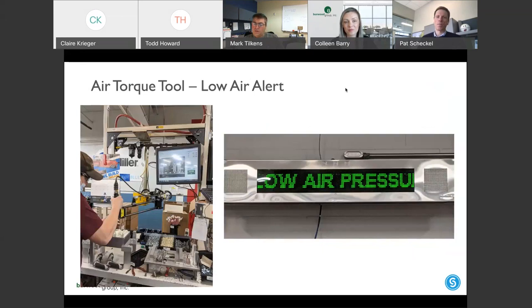So when we got into InformaCast, we did the big alert notifications, which was tornado, fire, and active shooter or active alert event going on. Those were kind of our targeted big three, and we quickly found a couple other unique scenarios. The one we're showing on the screen here now: during our manufacturing process, it's very important that certain torque specifications are met. And we had a scenario pop up right away where the air pressure in the building would get to a low level and nobody was really monitoring that.